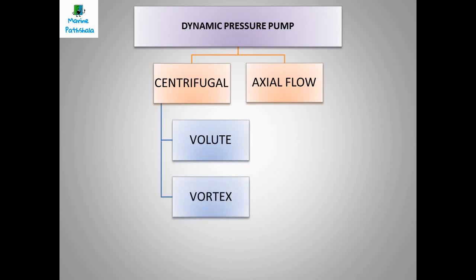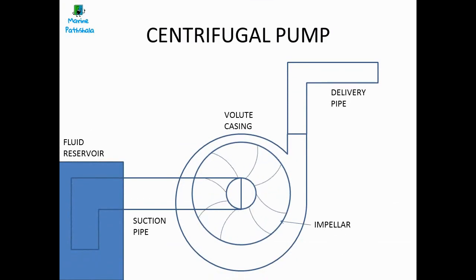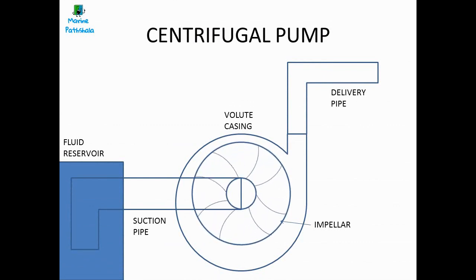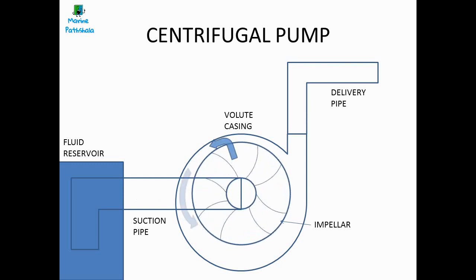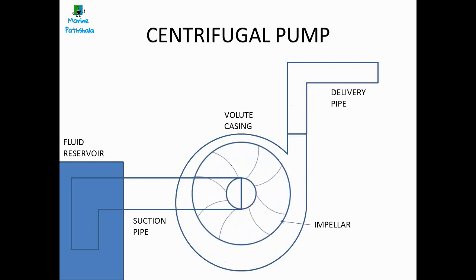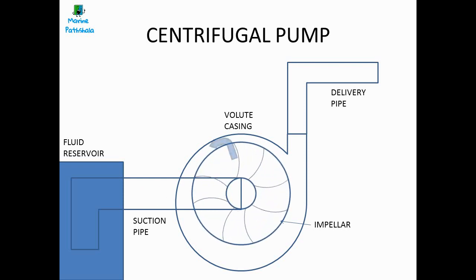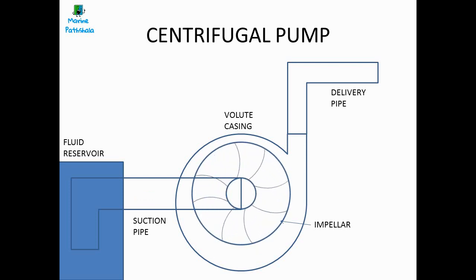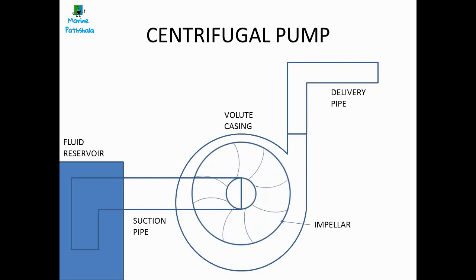Now let us understand how a centrifugal pump works. The pump consists of an impeller and volute casing. Fluid enters the pump body through the eye of the impeller. Due to the rotation of the impeller the fluid is turned, and the volute shape of the pump converts kinetic energy into pressure energy, and the fluid is discharged. Since the rotation of the impeller does not create vacuum initially, the fluid cannot be sucked into the eye and has to be brought to the eye of the pump — this is known as priming. Hence these pumps are not self-priming pumps.